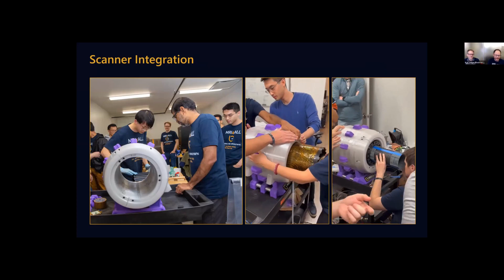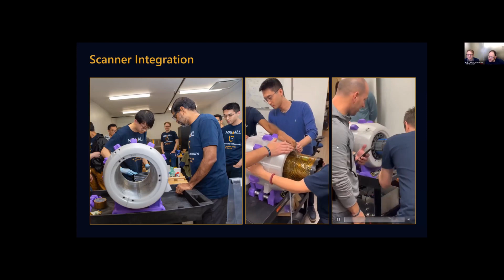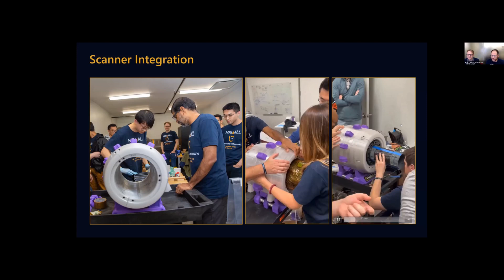Yeah, and then came the scanner integration. So this was the final day. This was the scanner integration. You can see here on the left, this was just before the cooling insert was placed inside the magnet. Then here in the middle, after the cooling was inserted, the tolerances for the gradient coil were quite slim, so we had to use a little bit of force to shove it inside and make sure it's straight in the isocenter. And then on the right side, we see the insertion of the passive shims and the RF coil into the bore.